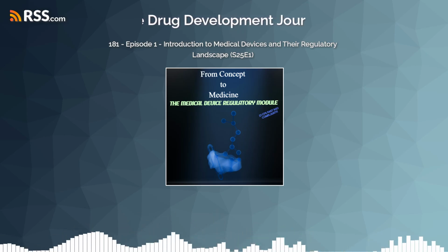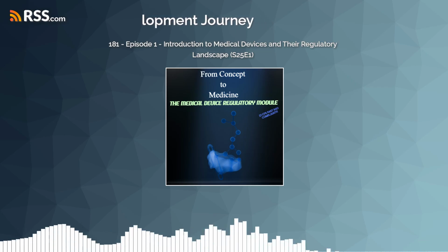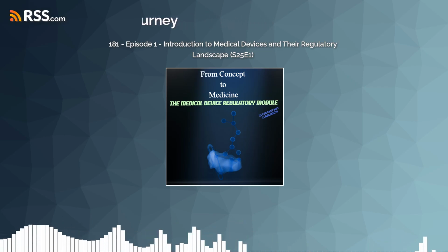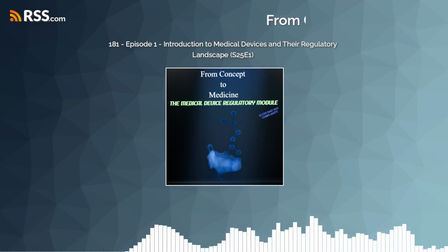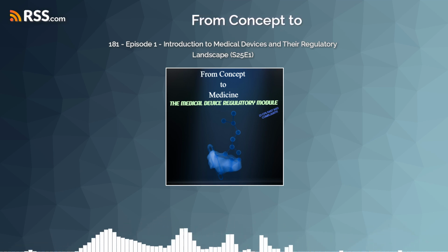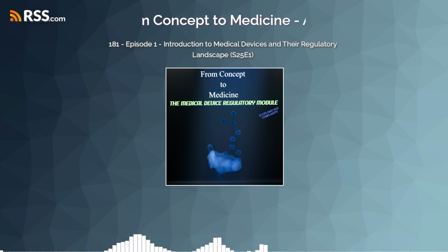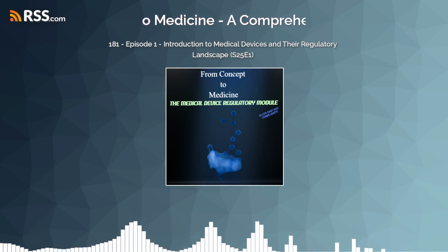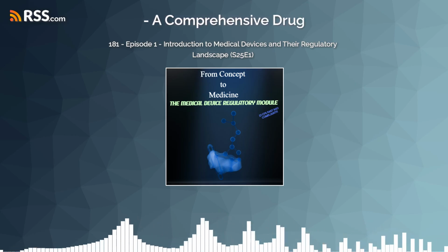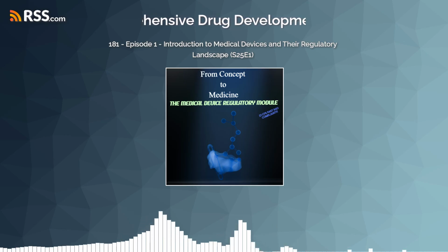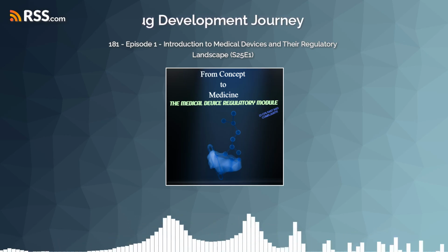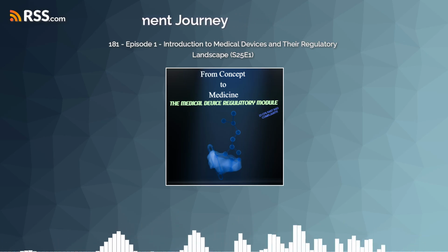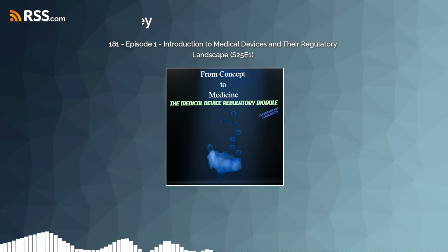And how do manufacturers make sure the design is actually going to work as intended before they start making thousands of them? That's where design verification and validation come in. Verification is about confirming that the design outputs, the drawings and specifications, meet the design inputs. Basically asking, did we design the device right? This usually involves tests, inspections, analyses. Okay, verification. Did we design it right?